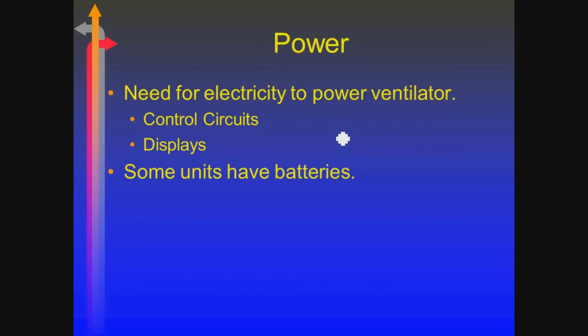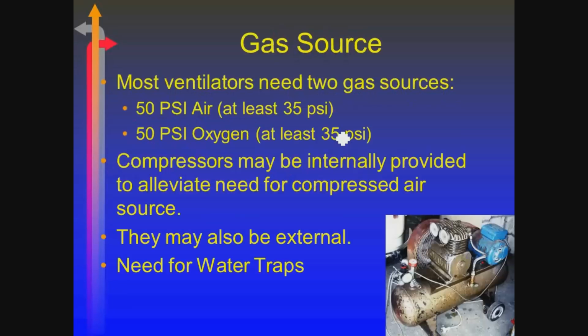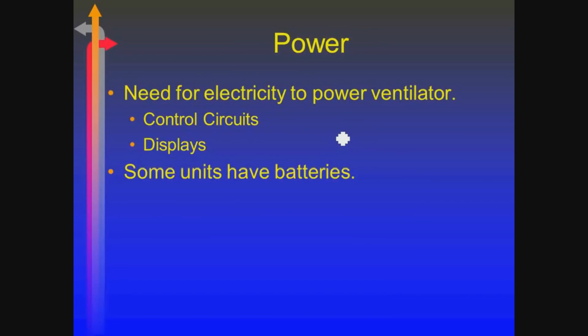All of them also need to not only be pneumatically powered, did I mention that word by the way? Pneumatically powered, electrically powered. The electrical power usually is not so much to run the machine, to generate gas flow. It's basically there to control the circuits and the monitors and displays and whatever. Some ventilators have a battery backup that will power the ventilator if you lose power. Some ventilators don't. So it really depends upon the manufacturer.